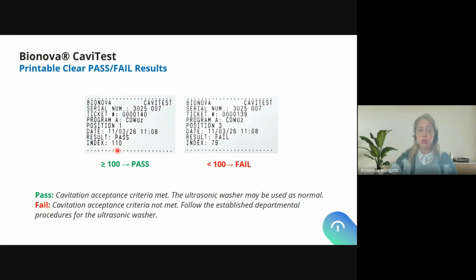Okay, so you can see here 110 is a pass. It will correspond to an accepted yellow color, and 79 is obviously less than 100, which means it is a failure, and we will also have the fail result printed. Okay, so the pass is a cavitation acceptance criteria met. The ultrasonic washer may be used as normal. Fail, the cavitation acceptance criteria is not met. So you have to follow the established departmental procedures for the ultrasonic washer and decide what to do with the machine.